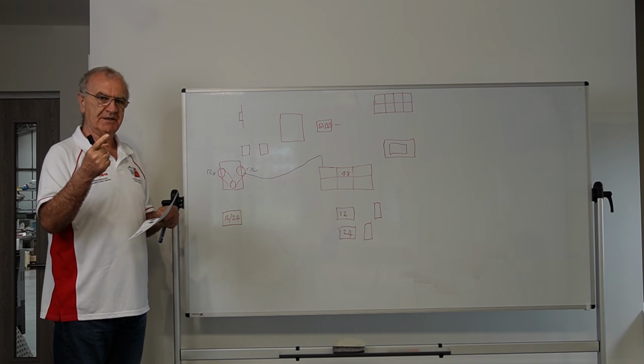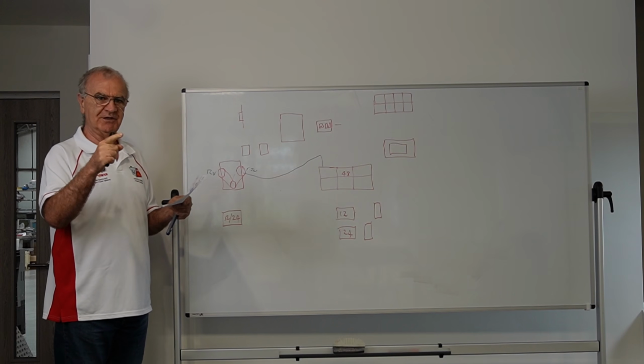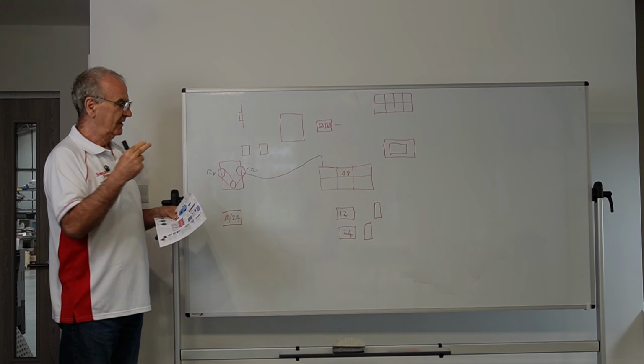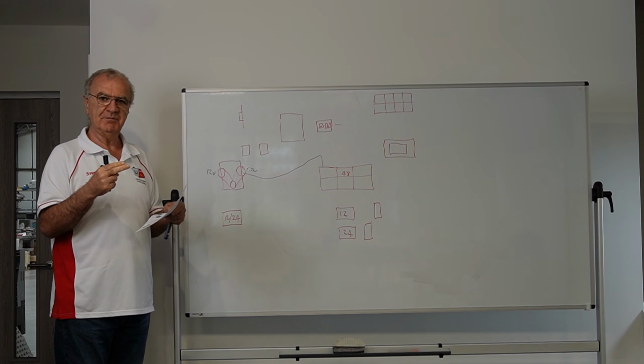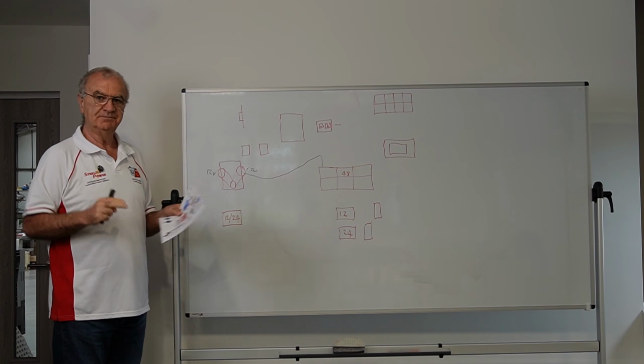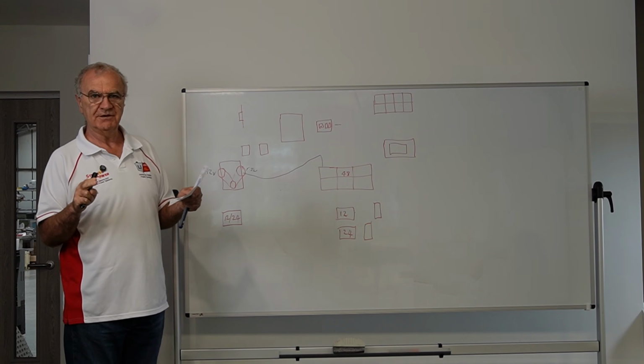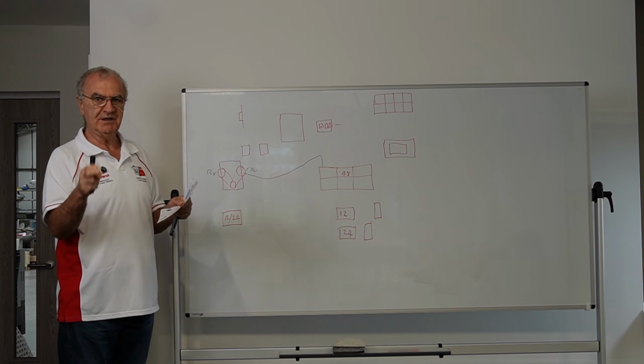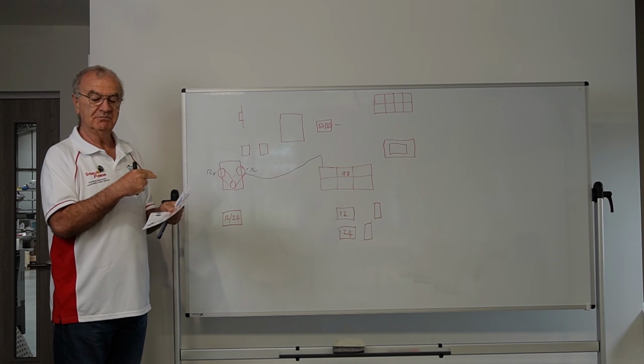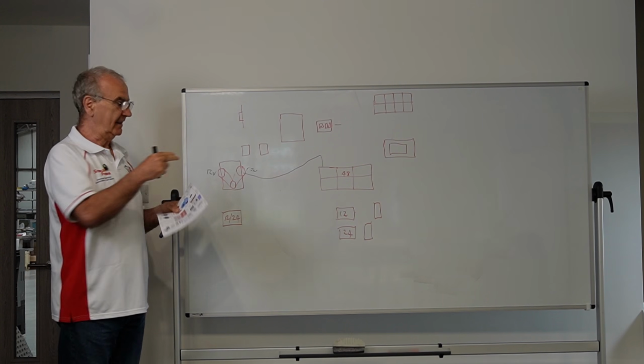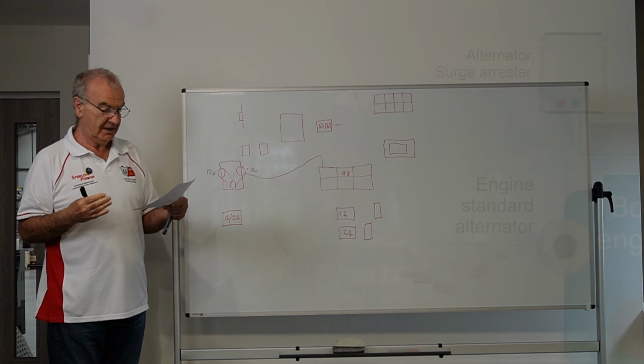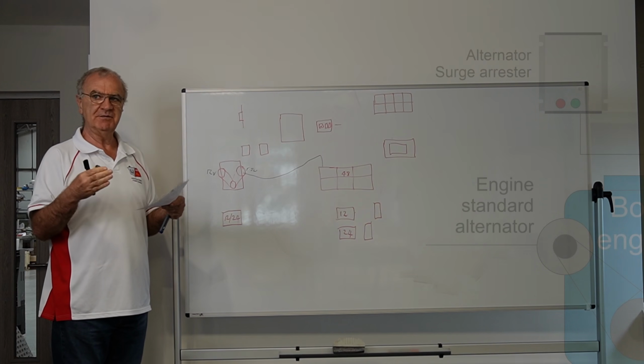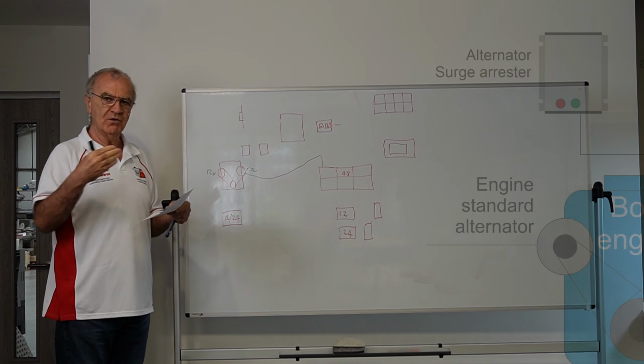One is firing the alternator up, switching it on and off with 12 or 24 volts. The second is the BMS on the lithium batteries will just instantly stop the odd time, then come back on again, then stop again, come back on again, which will destroy your regulator and anything else connected to the system. The third thing is purely the current limiting, where the thing is overworking.